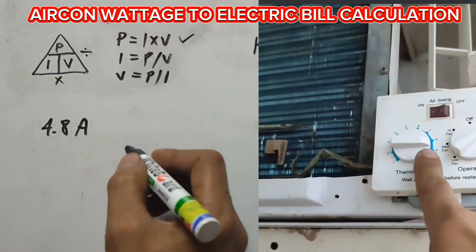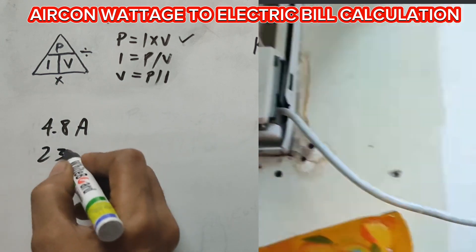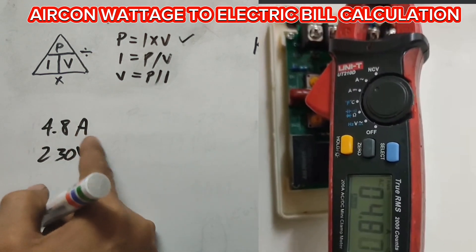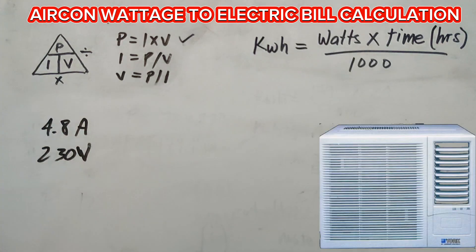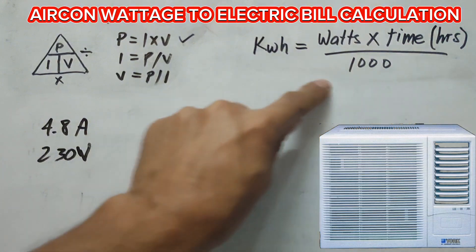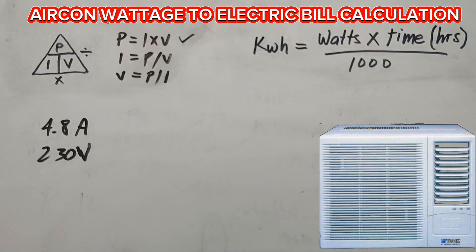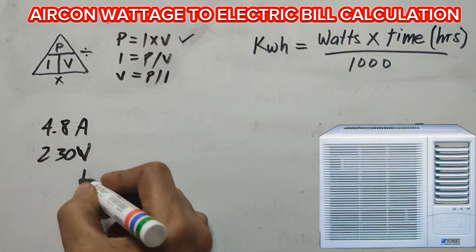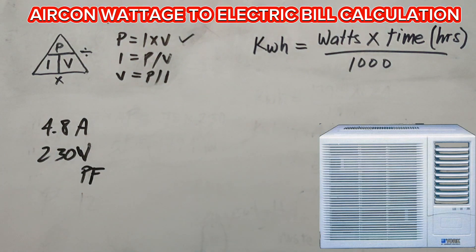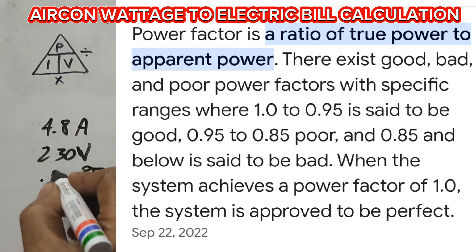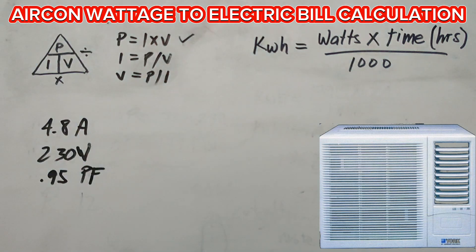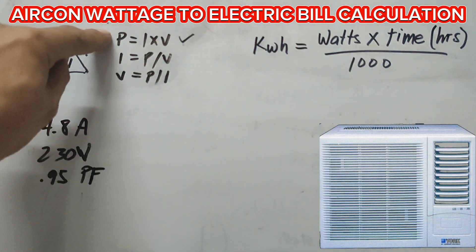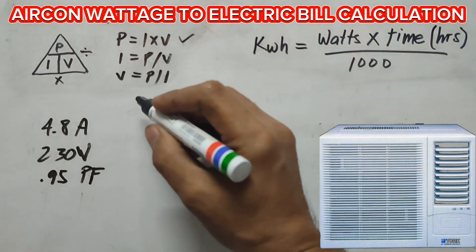The voltage is 230V. Since that is given, the missing value is P, which is the power measured in watts. We need that watt value in our formula. Some suggest that the compressor is a motor with inductance, therefore we're going to use a power factor. The value of power factor I choose is 0.95 — a good power factor ranges from 0.85 to 1.